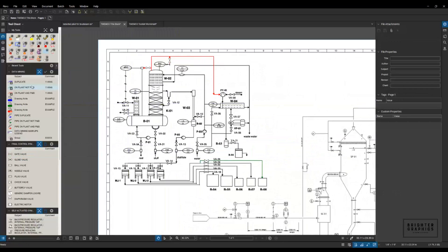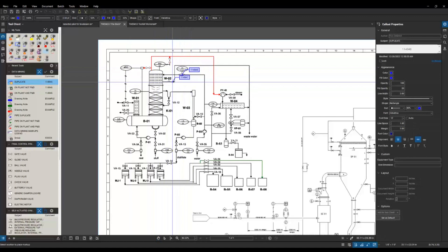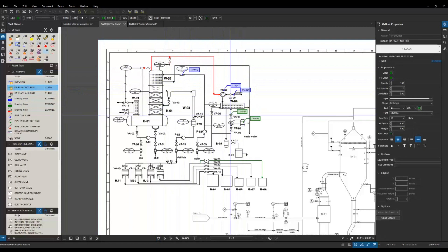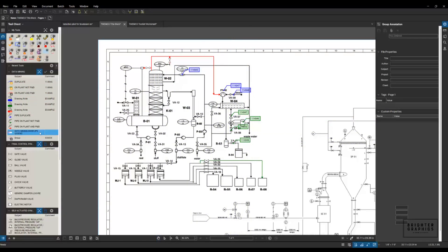We're starting to collect our data in here. So let's place some of these sequences. In this particular tool set, blue means it's a duplicate, green means it's on plant but not on P&ID, and red means it's on plant and P&ID. So we can go and place these again, just like we did on the other sheet, putting them in as we check these. And then we can always go back and clean these up — move these arrows around after we get back to the office.